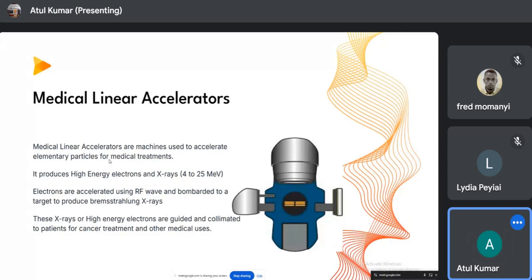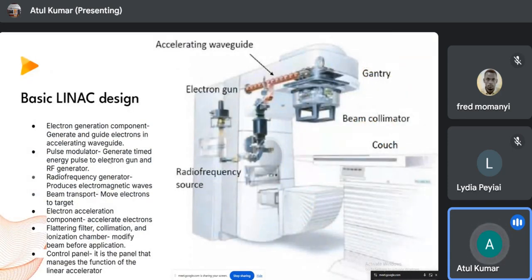So what is the basic design? The basic design of a LINAC from inside looks something like this. You have a radio frequency source. That radio frequency source can be a magnetron or a klystron, based on the design of the LINAC. That radio frequency is sent to a metallic waveguide, usually made of very high engineered, very smooth copper, and there are several cavities inside it.